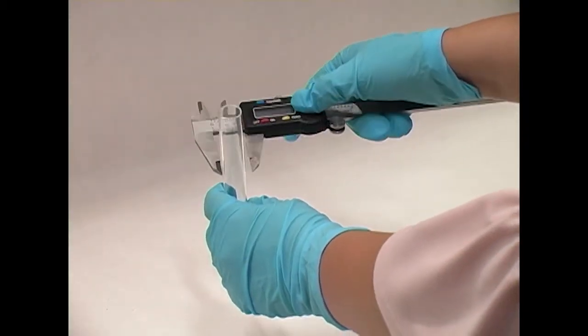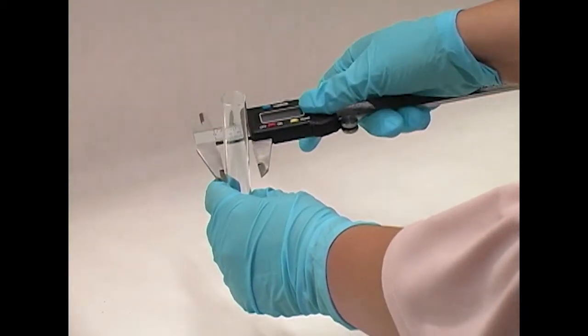The goal is to arrive at the largest outside diameter of three or more sample test tubes rounded up to the nearest 0.1mm.